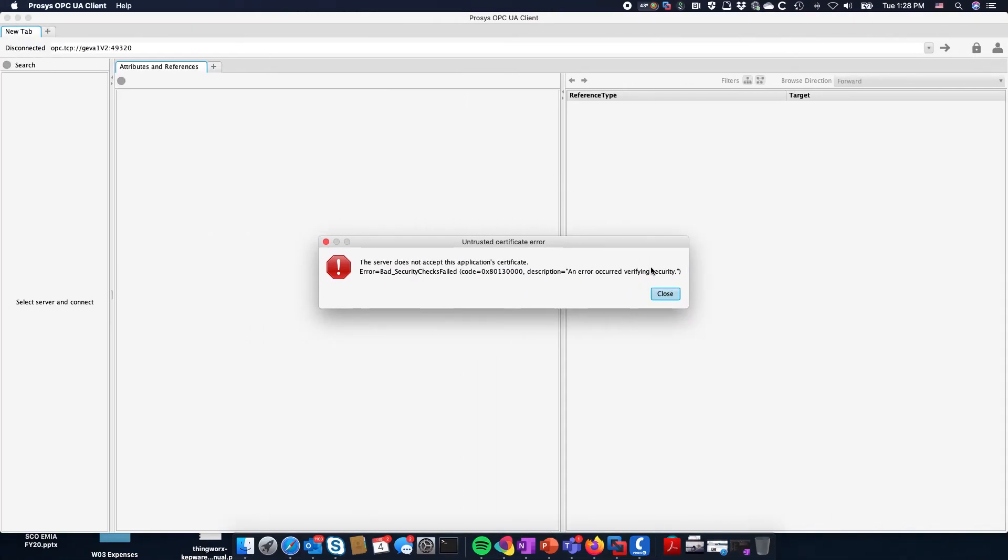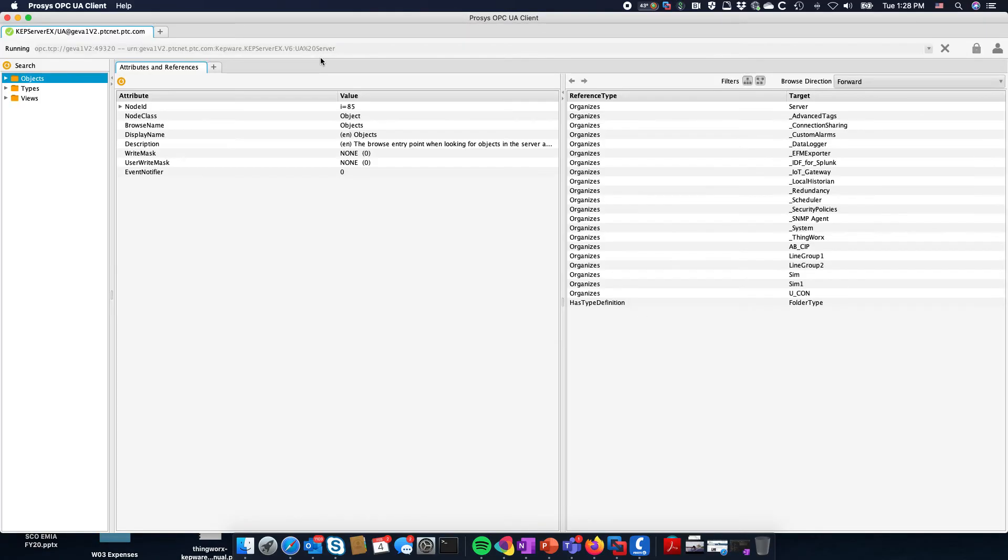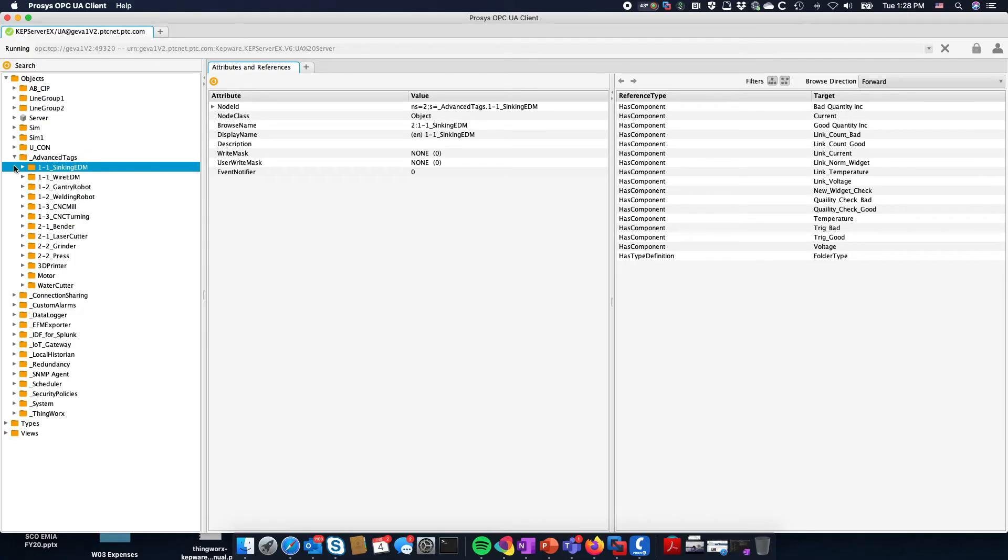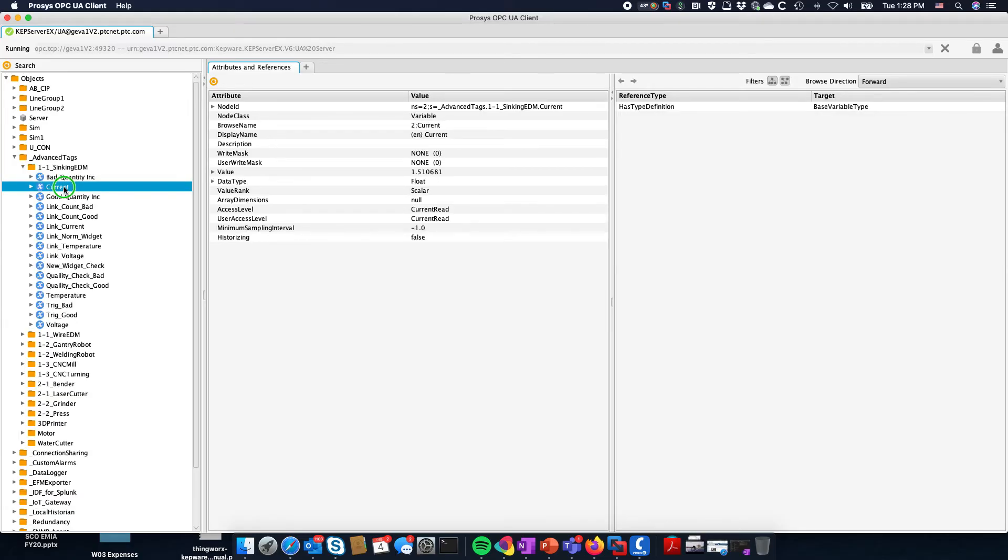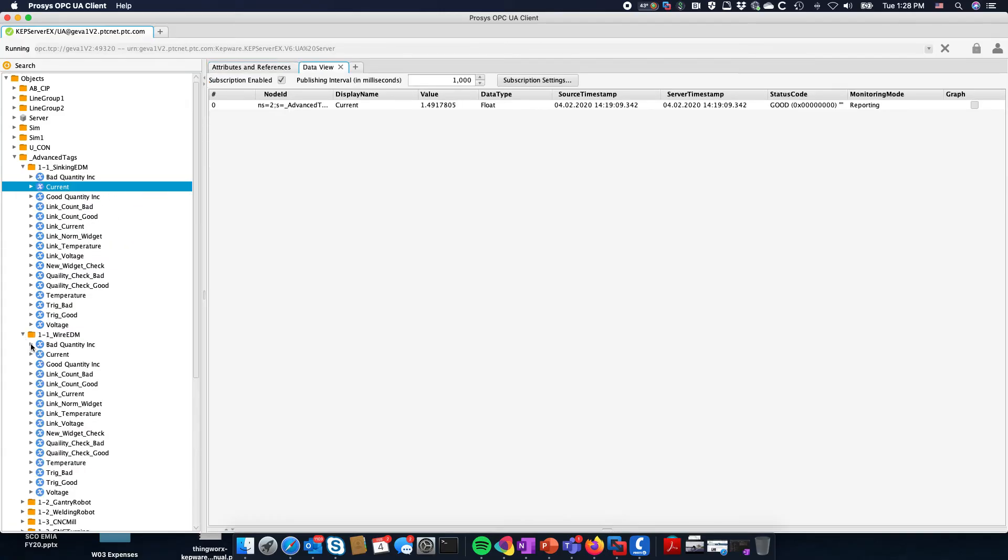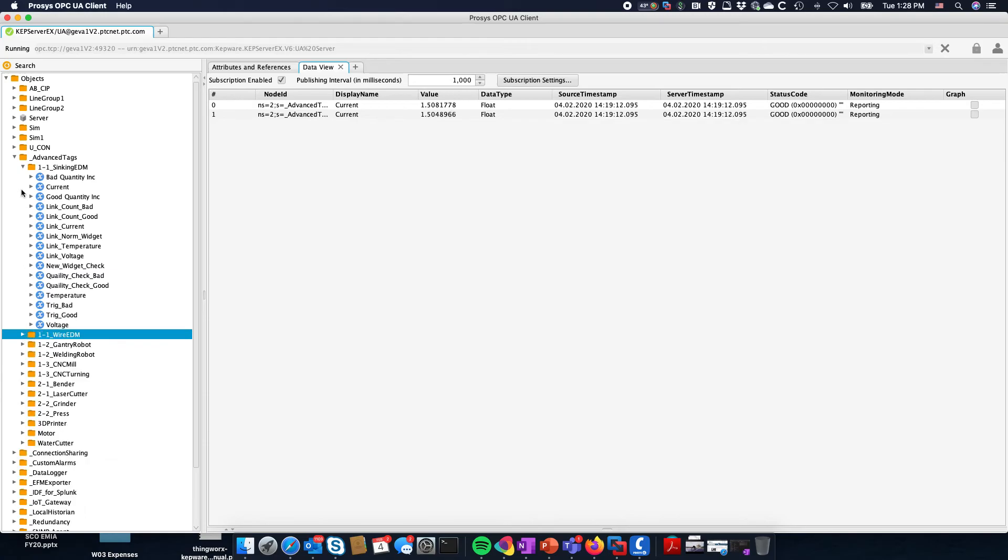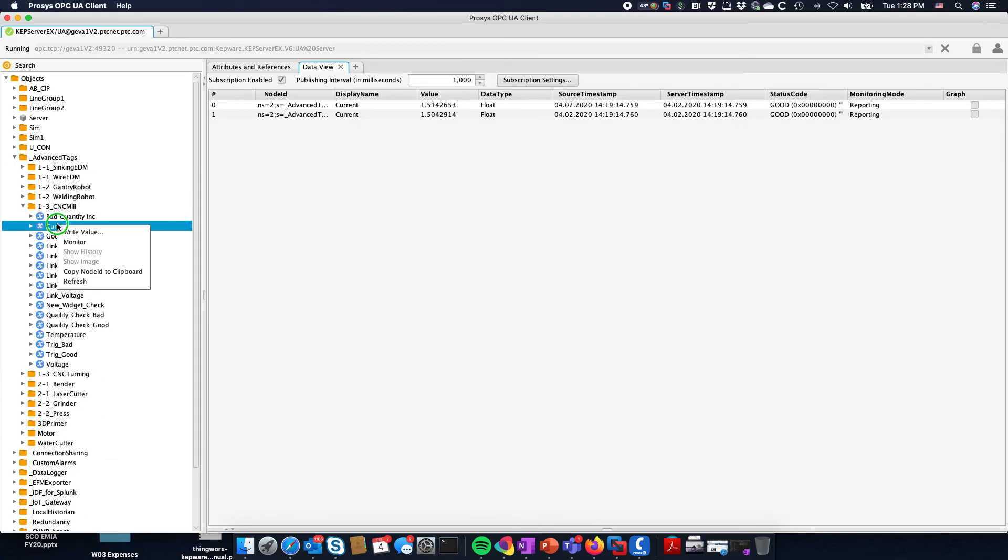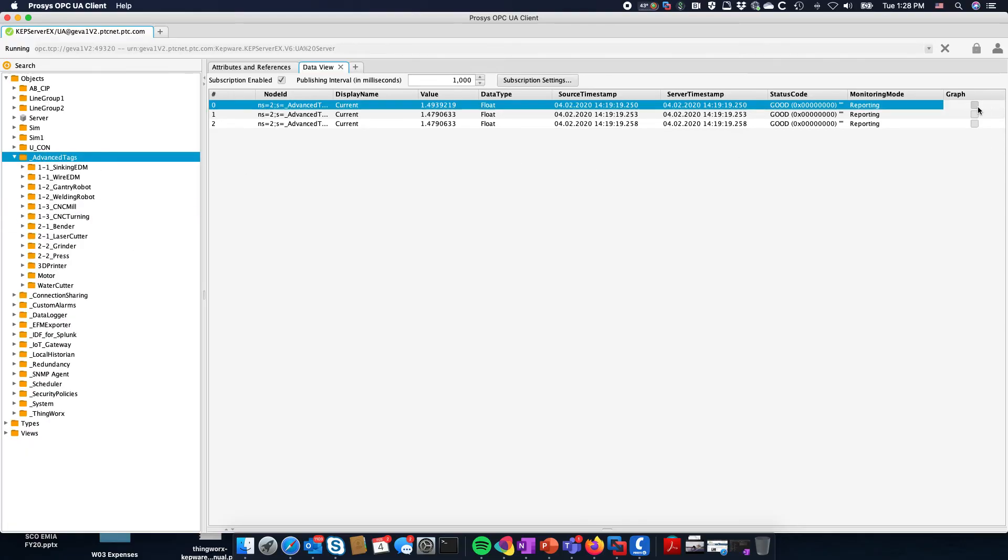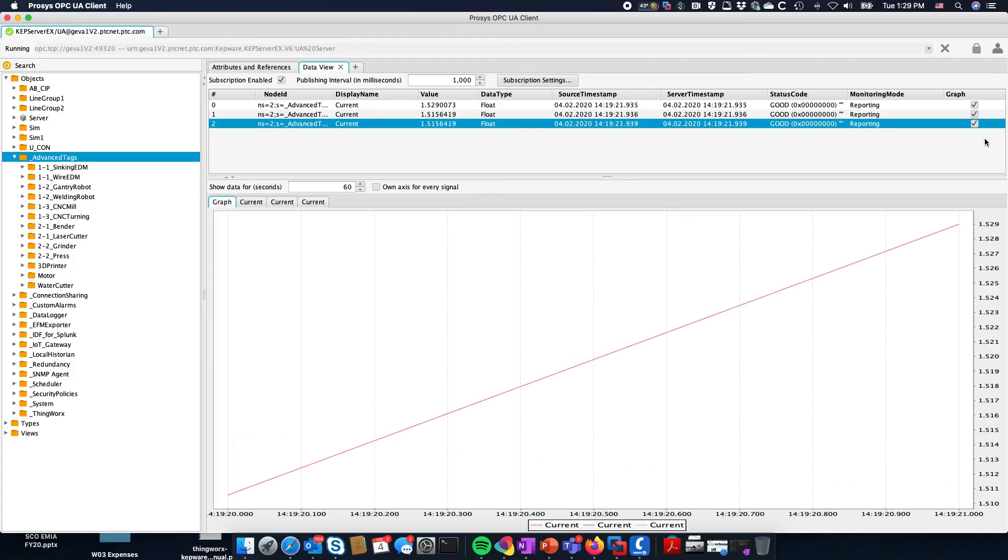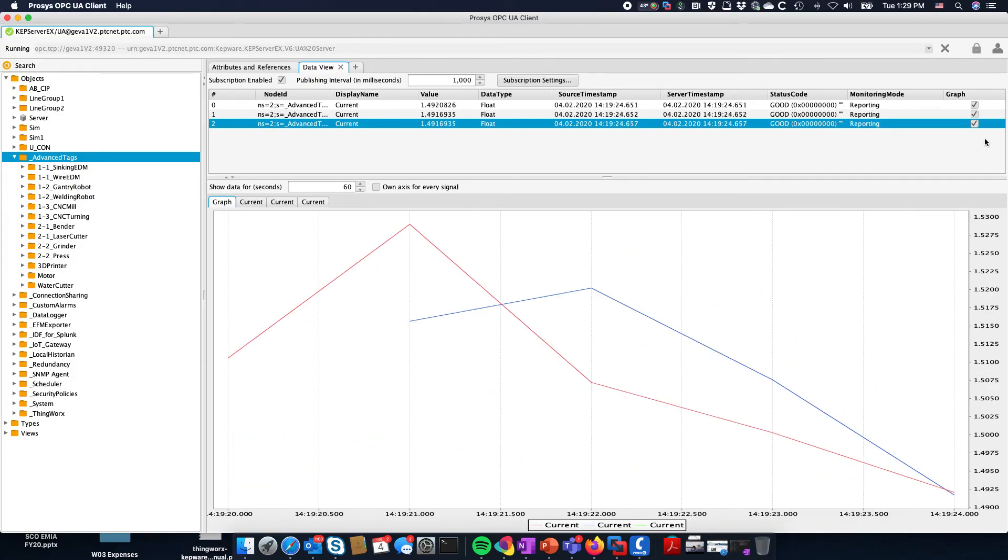I need to go back into Kepware, reinitialize it, and come back over to the Prosys OPC UA client and reinitiate the communication. We can see that we get connected to it. Now I can essentially browse my OPC server. Let's take some current values and monitor them.